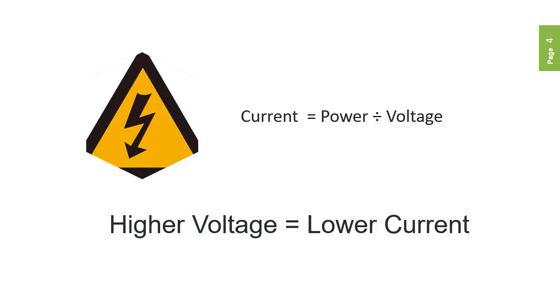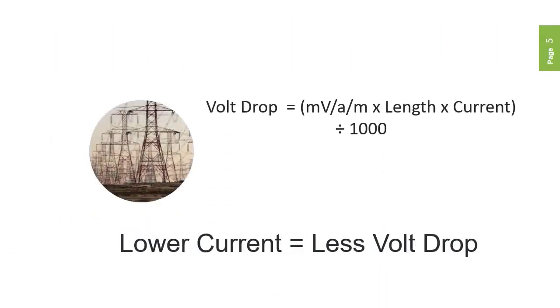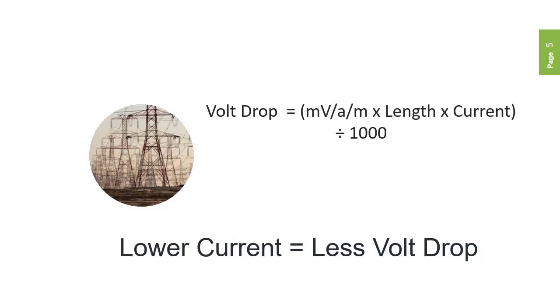This reduces the cost of the cables and also reduces the weight of the conductors hanging from the pylons. And secondly, this lower current also reduces the amount of volt drop present over long distances, as voltage drop equals millivolts per ampere per metre, times length, times current — which we've massively reduced — divided by 1,000.